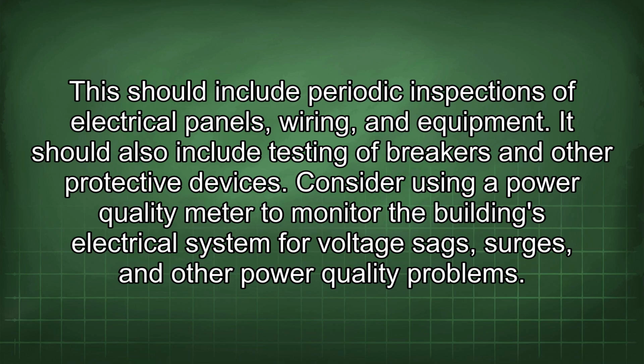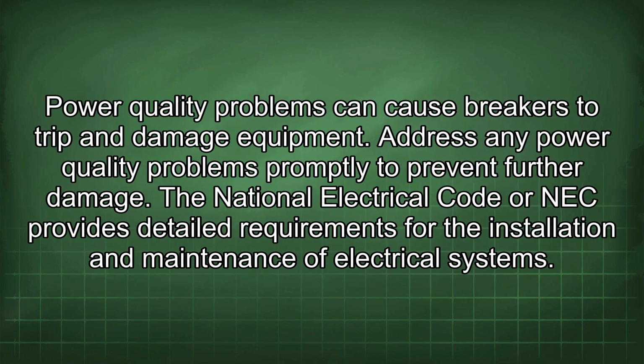Consider using a power quality meter to monitor the building's electrical system for voltage sags, surges, and other power quality problems. Power quality problems can cause breakers to trip and damage equipment. Address any power quality problems promptly to prevent further damage.